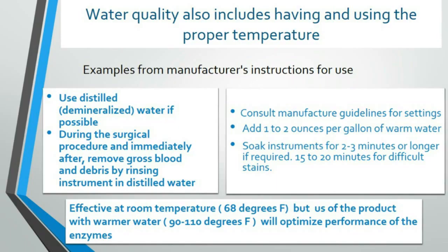So water quality also includes having and using the proper temperature. Examples from instructions for use, I just have a few here. Use distilled, demineralized water if possible. So that comes out of an IFU. During the surgical procedure and immediately after, remove gross blood and debris, rinsing the instrument in distilled water. That's probably something that's very susceptible to rusting and things like that, and they're trying to use the most treated water that they can.